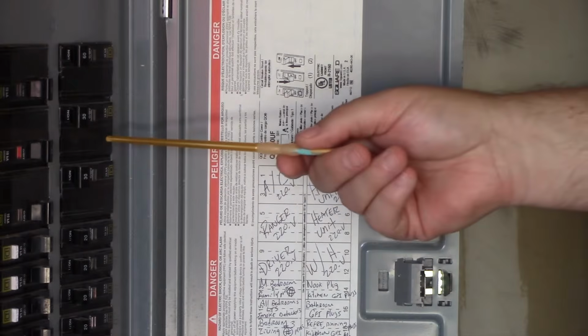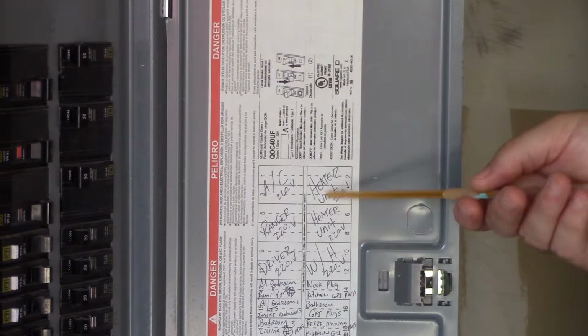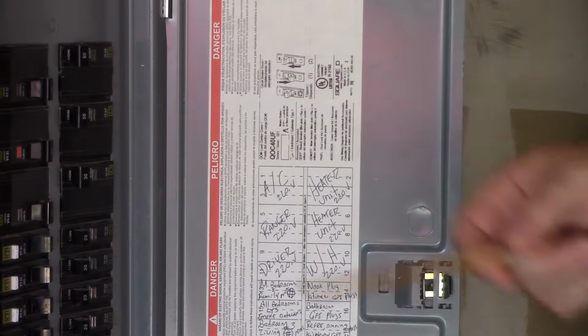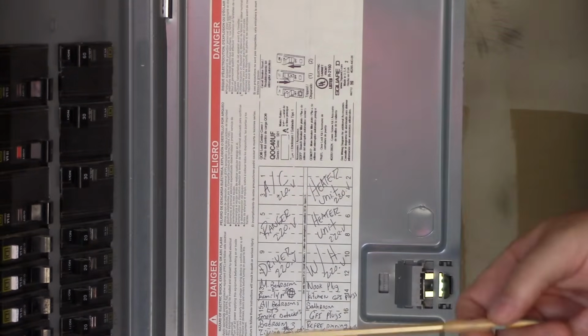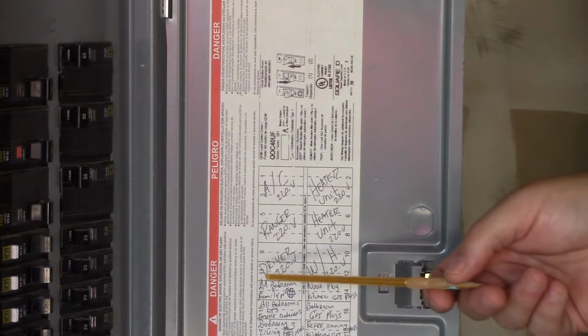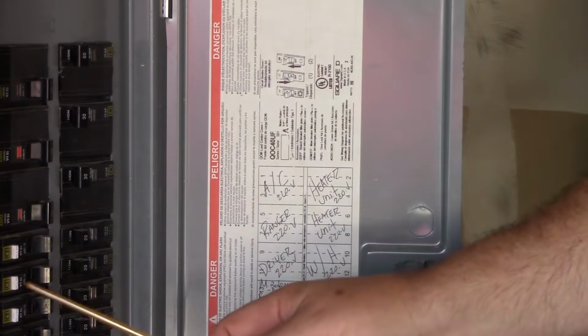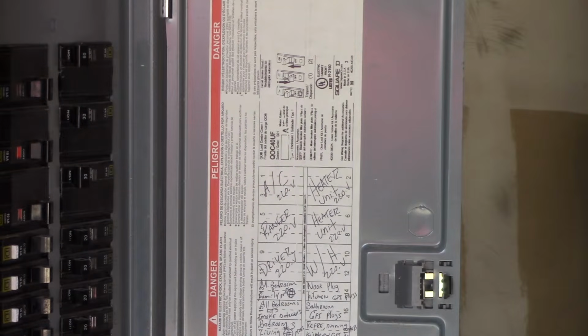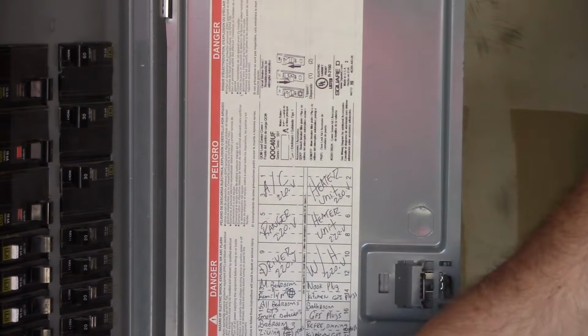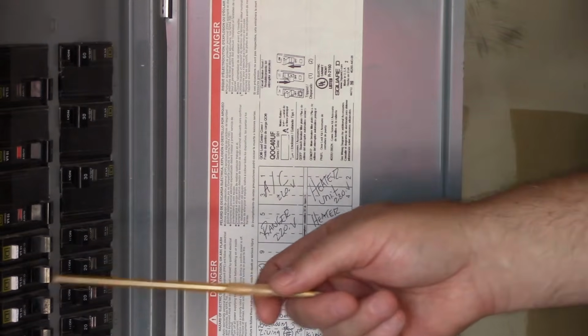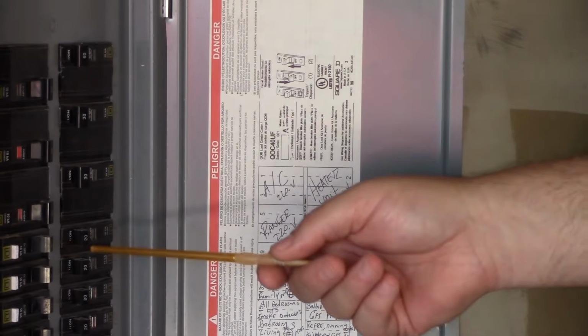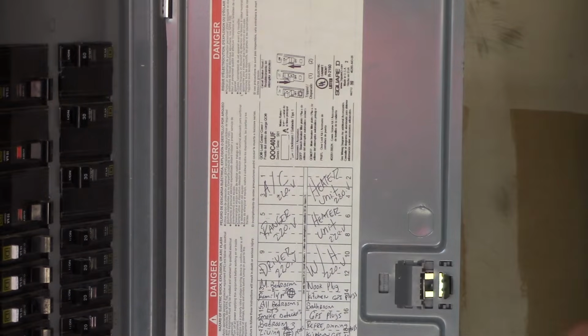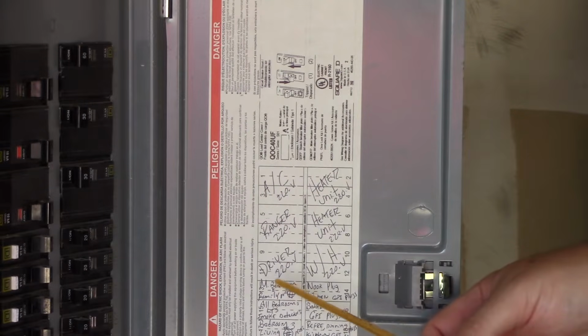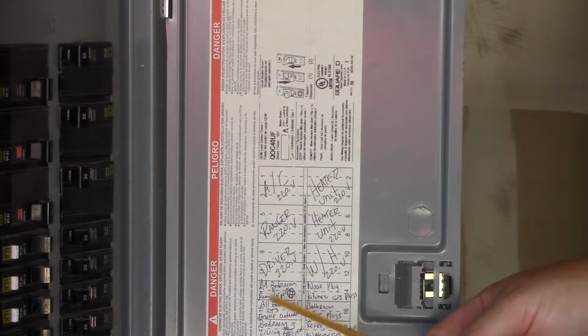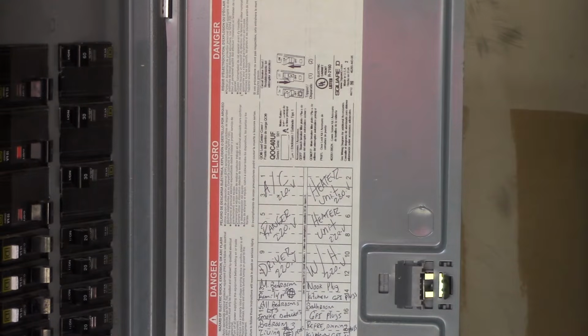The heaters, we're looking at a 30 amp for that unit. Here's a 60 for this, so we want to make sure the conductors correspond when we look into it. AC again is a 50, range is a 40, dryer is a 30, and of course then you have all these other circuit breakers that are associated here. Remember, these are 20 amp here, these are 15 amps here. When we look at them, we want to make sure the conductors terminated on them are the right size for this type of circuit breaker and their rating. But in this directory, we want to look for descriptive things. For example, if it says master bedroom, that one's pretty easy because there's probably only one master. In this house, there's only one master.